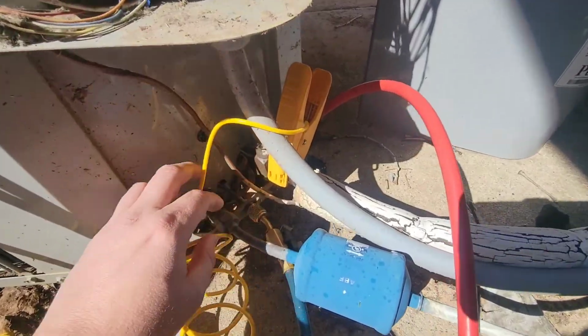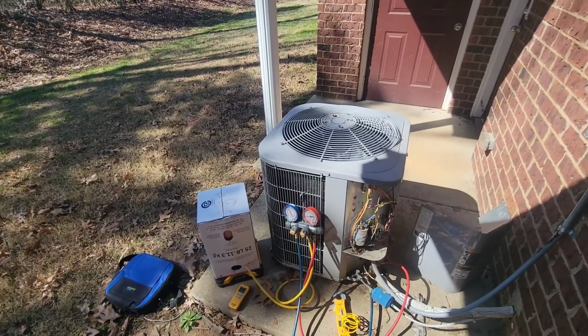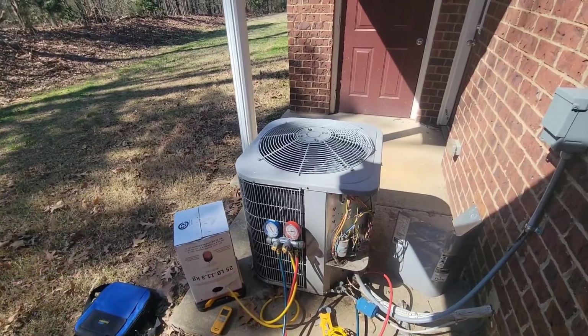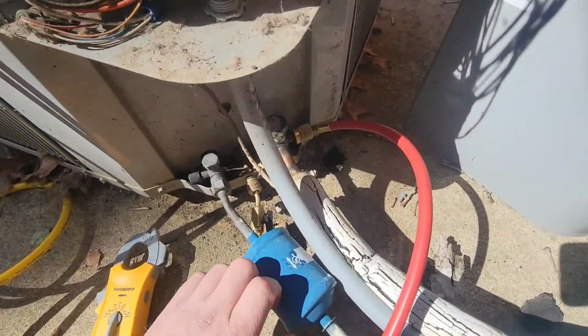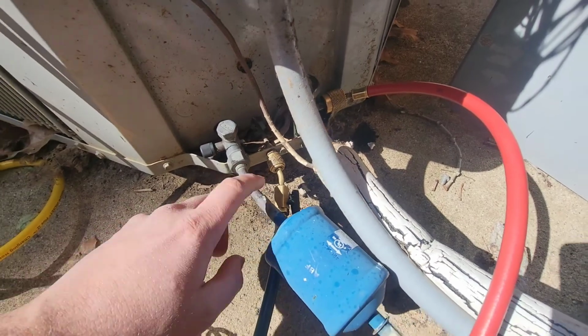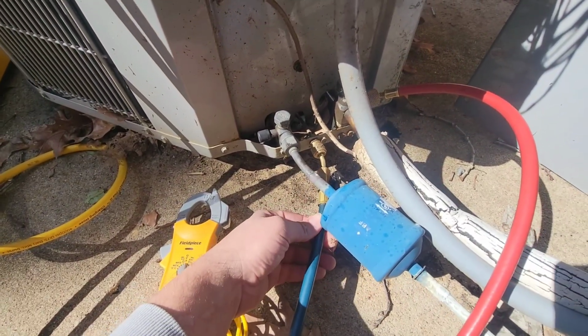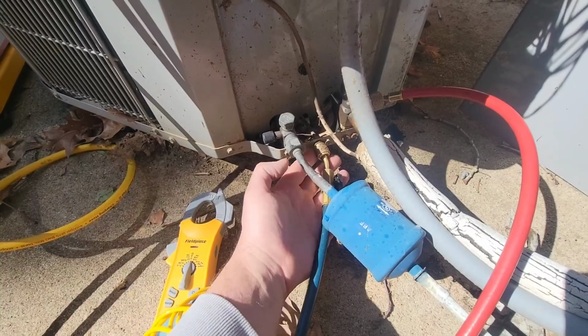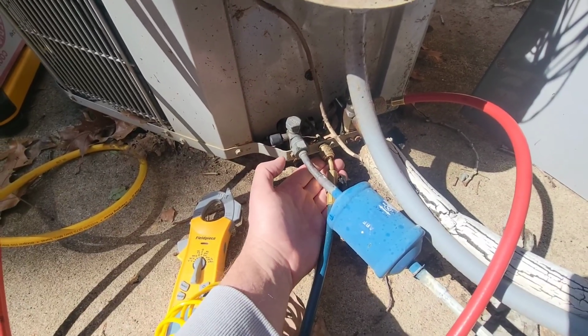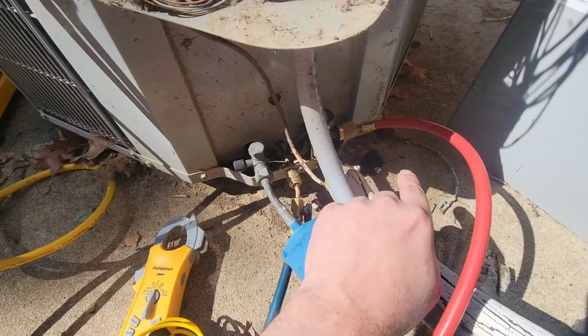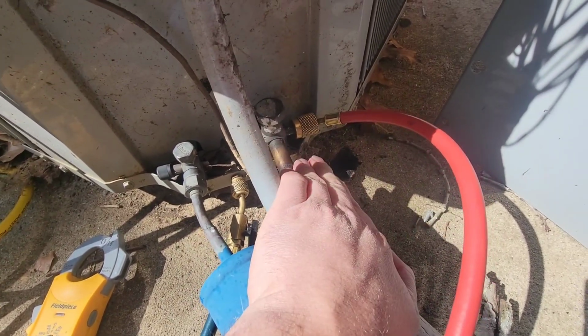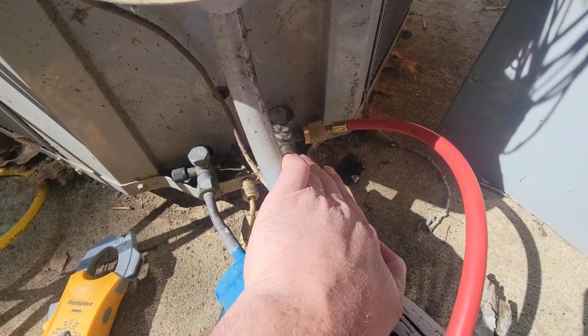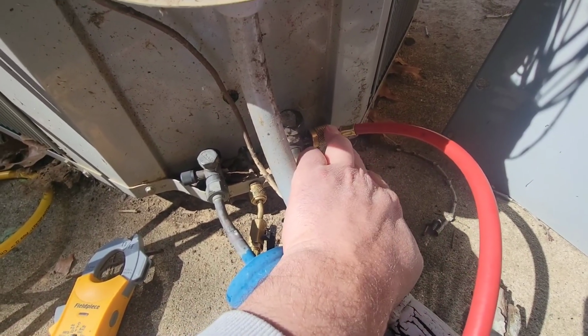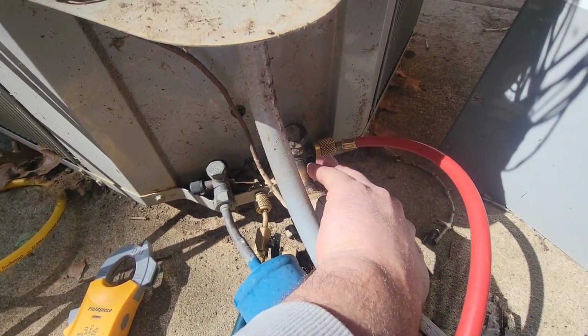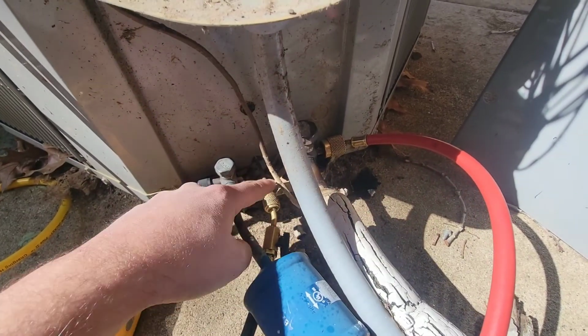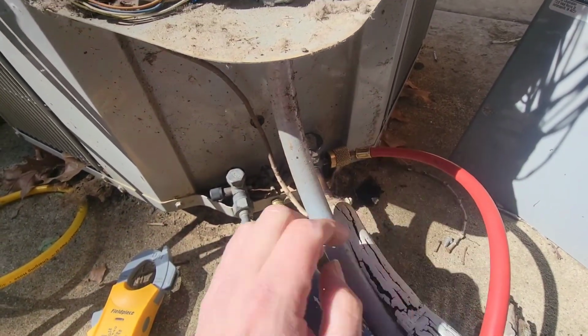Let me show you how my gauges are hooked up. Got the breaker shut off because I don't want the unit to just set and cut on and cut off and cut on and cut off. Obviously it's low on pressure and we're gonna charge it. I'm going to talk to you about how I have the gauges hooked up. So low side gauge goes to the port that goes to the suction line of the compressor. So we're measuring the suction pressure here with our low side hose hooked to our low side gauge. Then this line right here is the hot gas vapor line. And that's why we have our high side hose hooked here. During the cooling operation, when we're trying to measure pressures in the cooling mode, this hose would be hooked here, and then this hose would be hooked here.